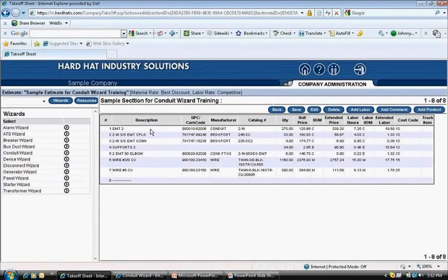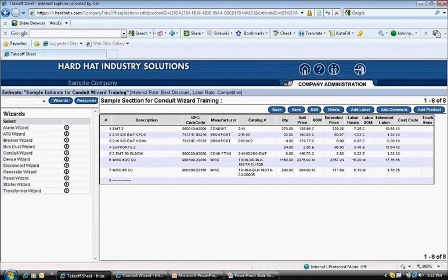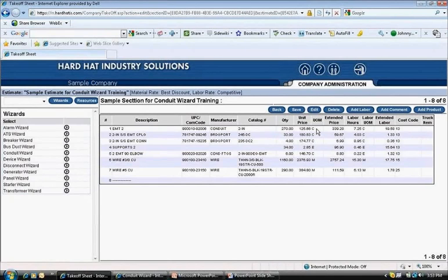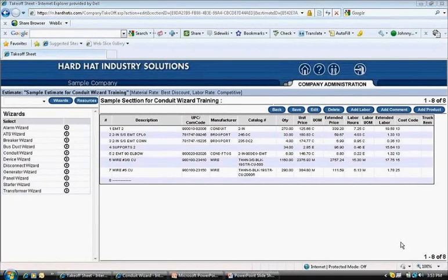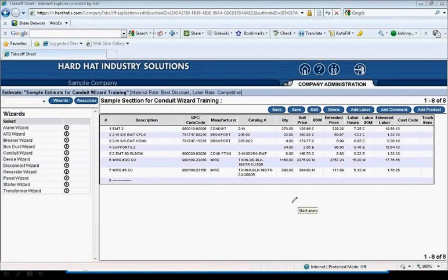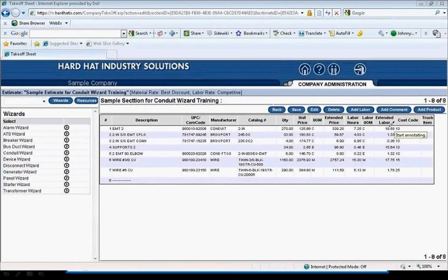This is what was just entered on the top line. Line 1 is the EMT conduit. Looking over to the right is the catalog number of the material, the quantity of material, which is 270 feet, and the unit price of the material. Next to that is the unit of measure. On the same line to the right, the display for labor hours plus unit of measure. Finally, at the far right is the extended labor or the total labor to install all the conduit.